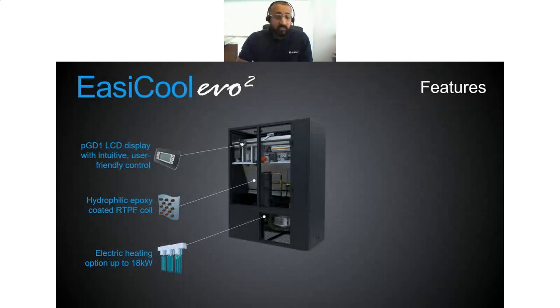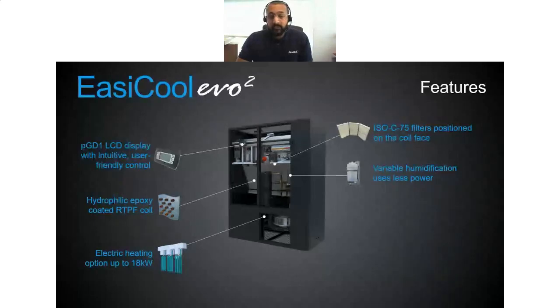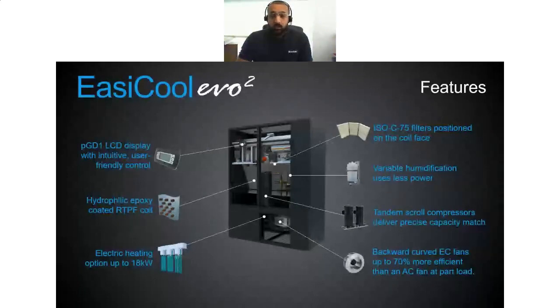We have electric heating options available up to 18 kilowatt. We have standard ISO C75, which is equivalent to G4 filters, positioned on the coil face. Electrode steam humidifier with variable humidification, with an option of standard and cleanable or disposable bottles, and different conductivity are available within the unit. We utilize tandem scroll compressors to enable part load and full load operation and to deliver precise capacity match. We have backward curved EC fans, up to 70% more efficient than the AC fan at part load operation.